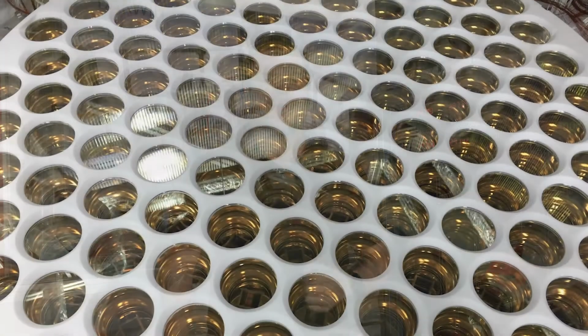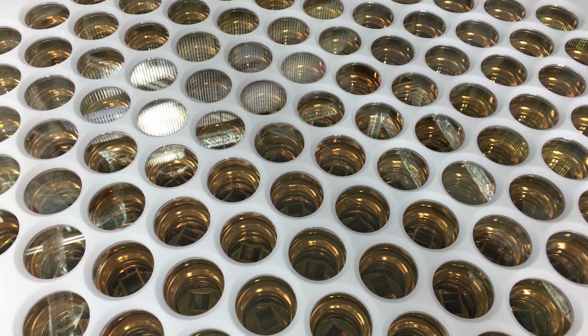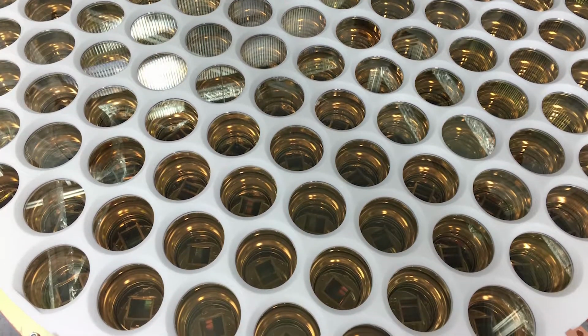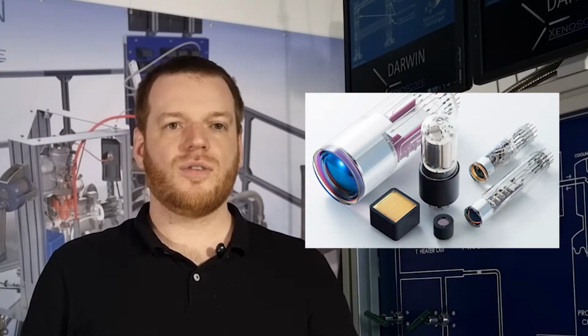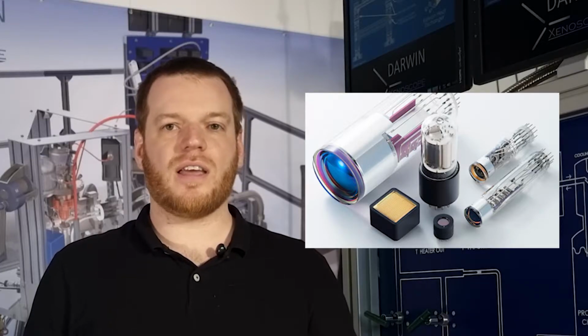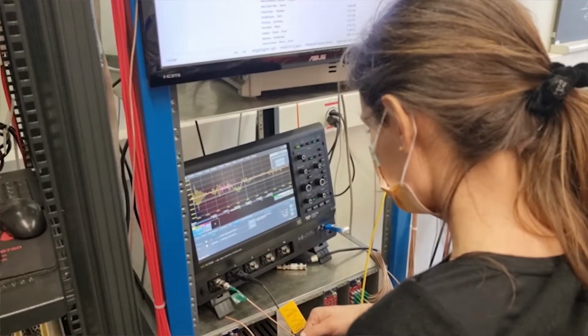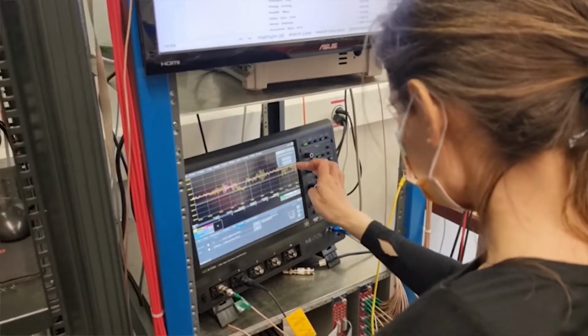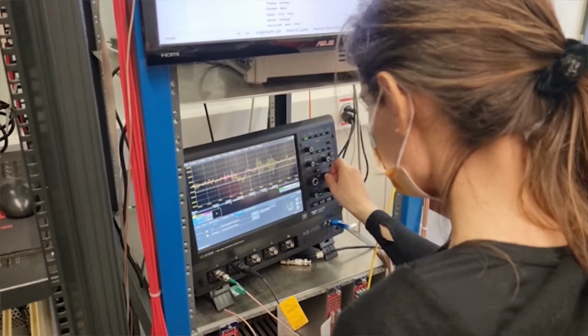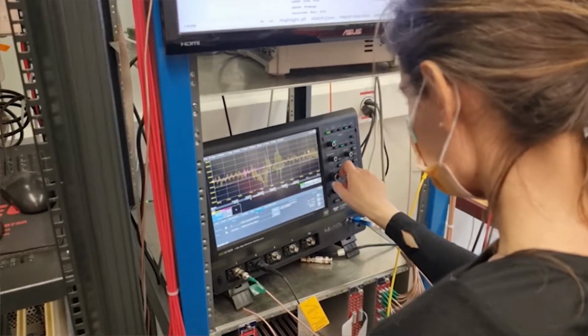The next two setups I will show here are used for photosensor testing. As you can see by simply looking at current dark matter experiments, photosensors play a major role in the hunt for dark matter by basically being the eyes of the detector. Needless to say, before commissioning sensors at large scales, our collaboration tests a multitude of sensor variants to ensure their high sensitivity at the wavelength of the light we want to detect, in our case in the VUV range. We also need to ensure their reliability in the long term and to ensure that their noise levels are low enough to make them sensitive to low-level signals.